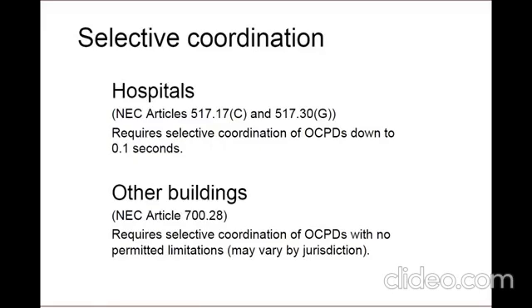In addition to selective coordination of overcurrent devices, 517.17(C) requires selective coordination of ground fault protection devices. When a hospital or building that contains critical care spaces or life support equipment includes ground fault protection per NEC 230.95 or 215.10, a second step of GFP is required to each downstream load.